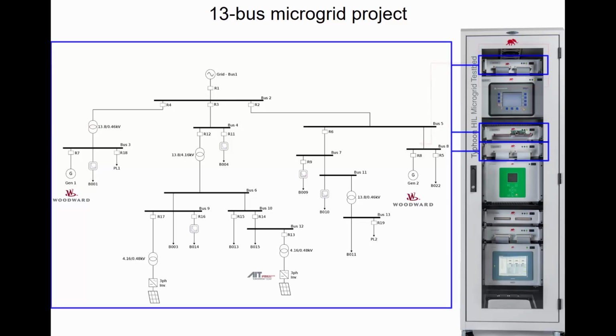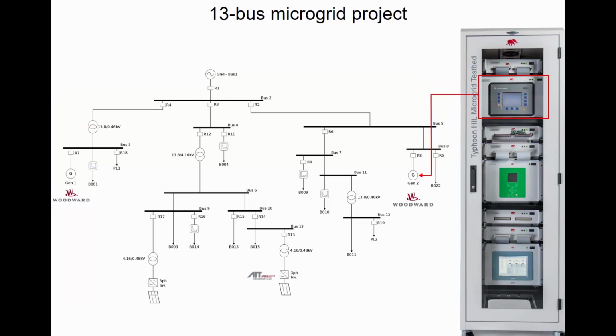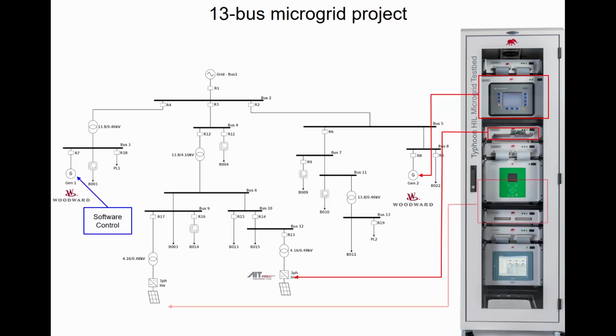The 4 MVA diesel genset, also called Gen 2, is controlled externally by a Woodward EasyGen 3000 controller. The 1 MVA genset, or Gen 1, is software controlled with control loops designed with the digital signal process blocks from our library. The 35 kW photovoltaic inverter is controlled by a firmware from Austrian Institute of Technology, or simply AIT, flashed in a TI Delfino board. The 25 kW PV inverter is controlled by a Hummingbird controller by Schneider.